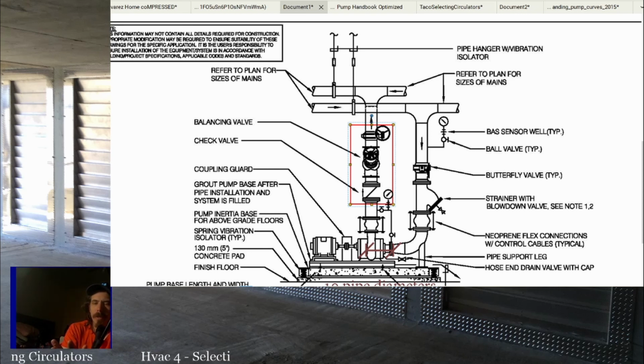I've only worked on a couple dry cooler pumps. They're expensive as hell because they're usually very high head, relatively low flow. As a matter of fact, I want to say that's probably the highest head pressure pump I ever worked on, was one for a Liebert thing. Right. Yeah, I can't remember. I want to say it's like 200 or 300 feet of head or something ridiculous. I'm like, Jesus criminy. It's a $1,000 pump.